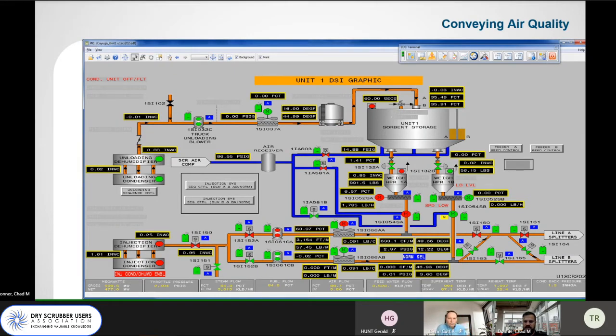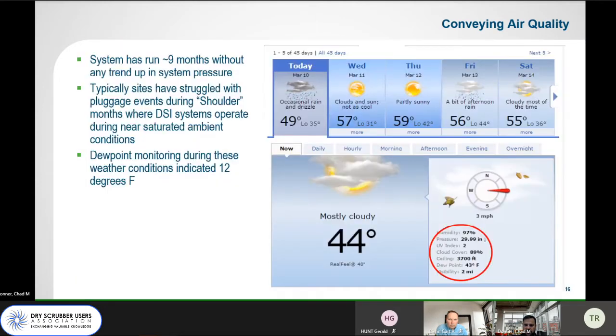This is an example of a DCS screenshot from the Cayuga station. You can see the dew point is running at 12 degrees Fahrenheit, and the ambient temperature is roughly 48 degrees. This is all the same day. Just for comparison's sake, I went to weather.com and got the outside ambient air conditions. The outside conditions were basically saturated with a high dew point. And if you remember from the DCS screenshot, the measured dew point in the conveying air was 12 degrees Fahrenheit.